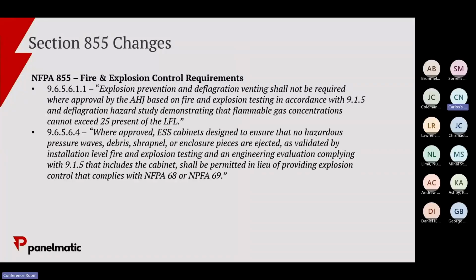A lot of this is talking about the cabinets, and you were talking about ESS cabinets as well. Those standard individual ones, because code traditionally used to say it was a large-scale energy storage system, those individual cabinets kind of skirted under the radar. So they were having similar issues where they would either explode or have thermal runaway events. They didn't have deflagration panels, so if they sealed up and then someone opened the panel, that inrush of oxygen would cause it to basically blow, and you'd shoot shrapnel.